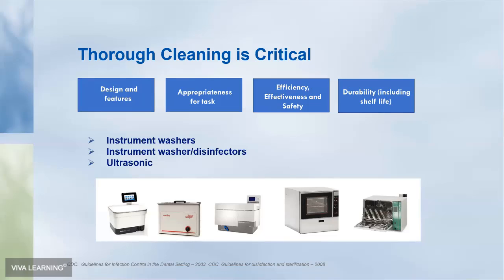So for cleaning, I only have 3 options up here: instrument washers, instrument washer disinfectors, and ultrasonic cleaners. We all know that manual cleaning exists. It is not recommended and it's discouraged unless required for spot cleaning or for a specific area of a specific device. So it should be avoided when possible, and automated instrument washers or washer disinfectors or semi-automated ultrasonic cleaners are recommended.